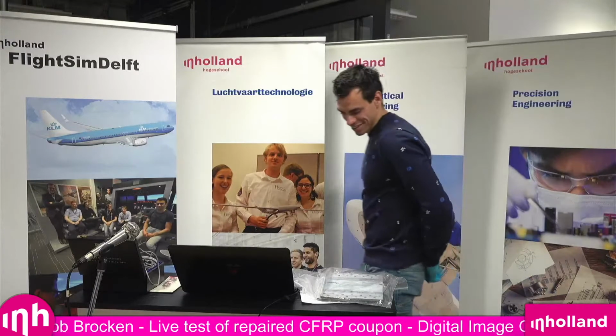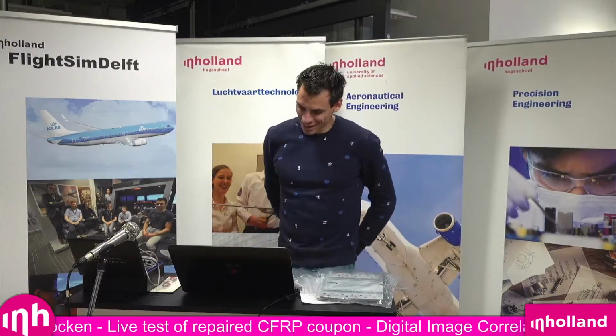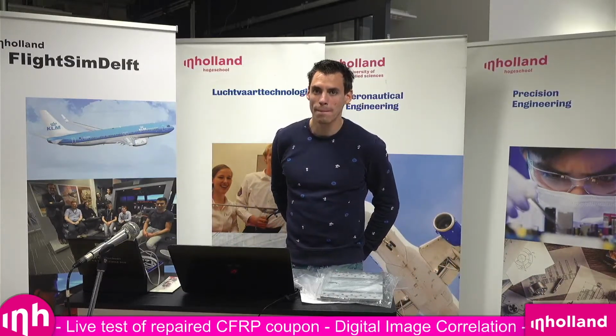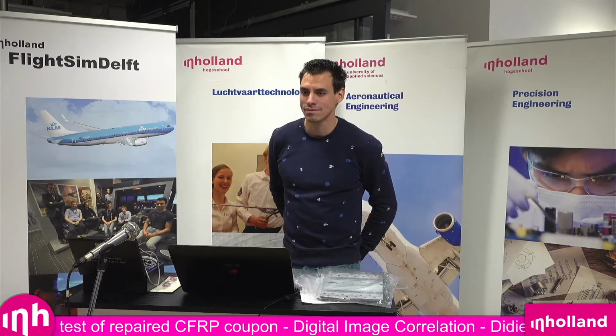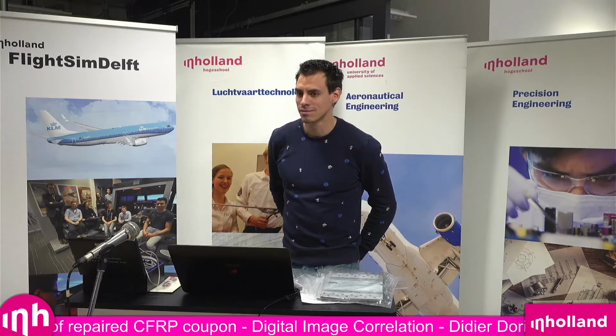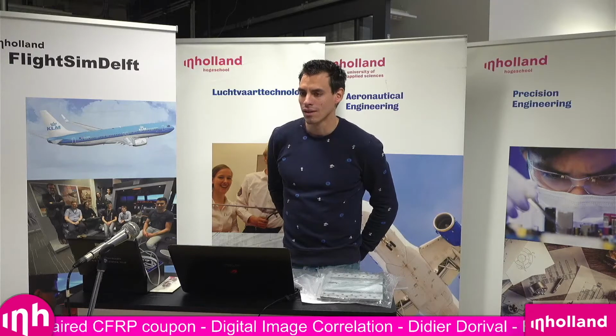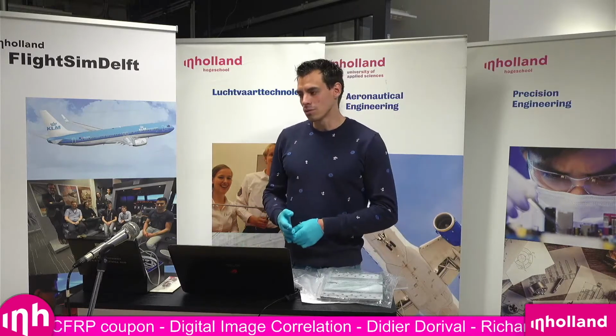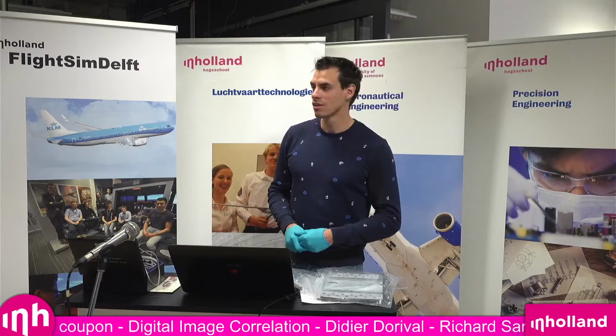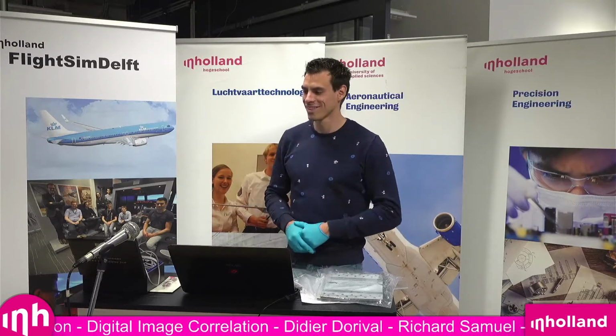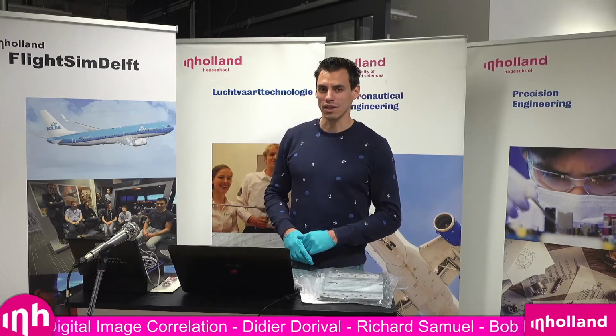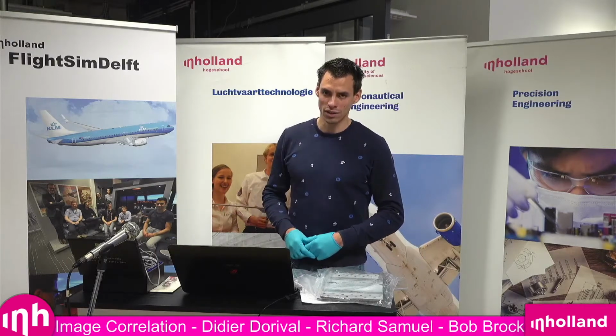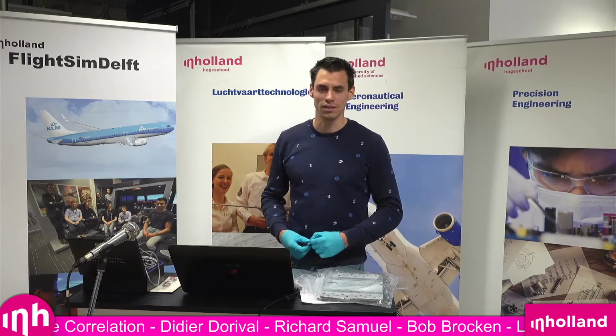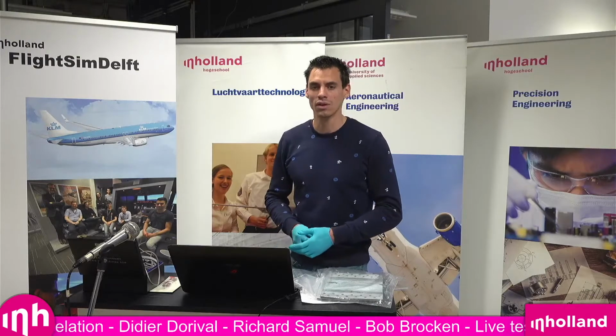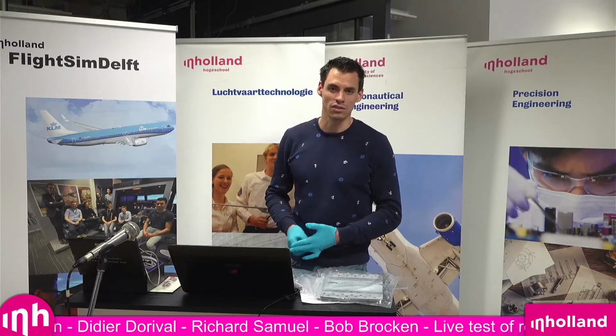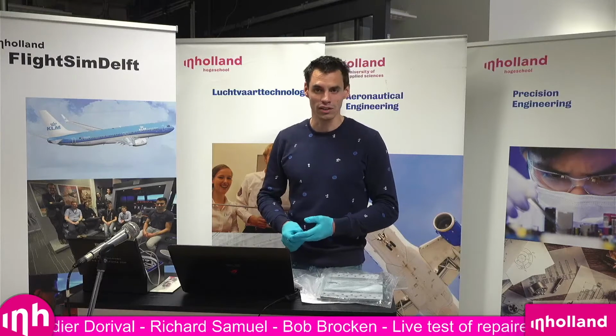Alright, so we have a question from G. What about certification for the aerospace industry? How do you think this will be possible and in what time frame? So there's a specific ISO standard, 9513, which is related to tensile testing, and specifically to measurement systems for the measurement of elongation or strain.